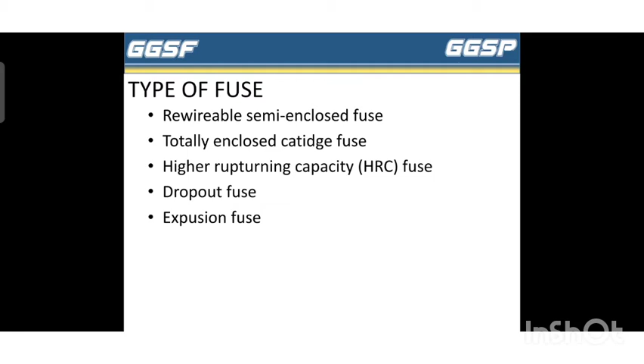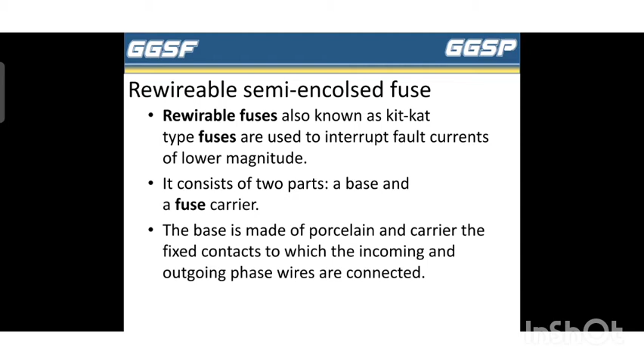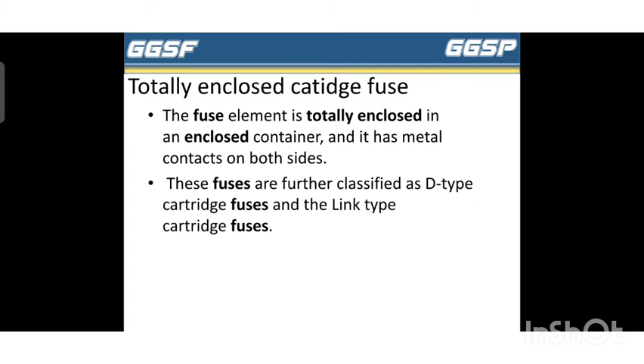Rewirable fuses, also known as kit-kat type fuses, are used to interrupt fault current of lower magnitude. It consists of two parts, a base and a fuse carrier. The base is made of porcelain and carries the fixed contacts to which the incoming and outgoing phase wires are connected. Totally enclosed cartridge fuse. The fuse element is totally enclosed in an enclosed container, and it has a metal contact on both sides. These fuses are further classified as D-type cartridge fuse and link type cartridge fuse.